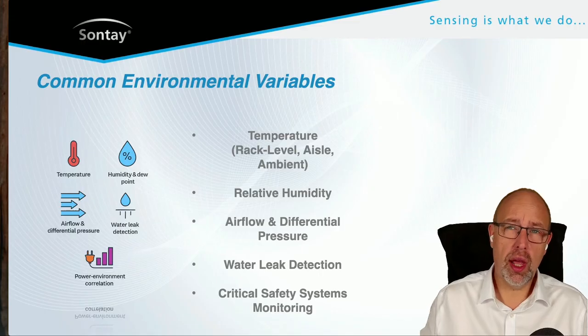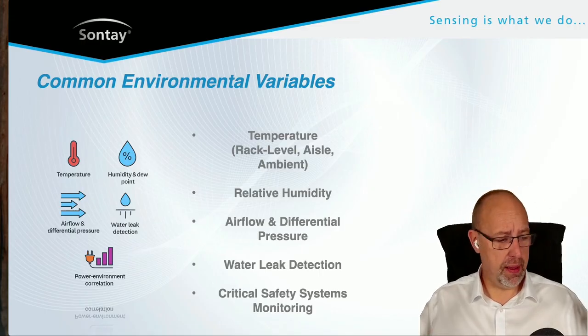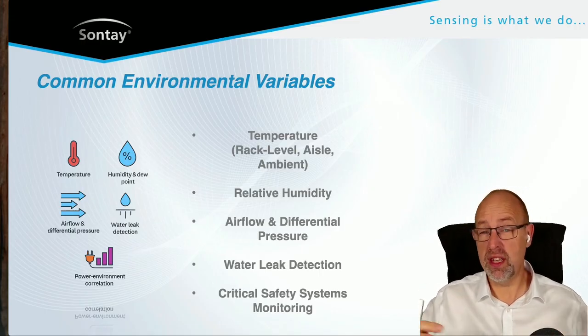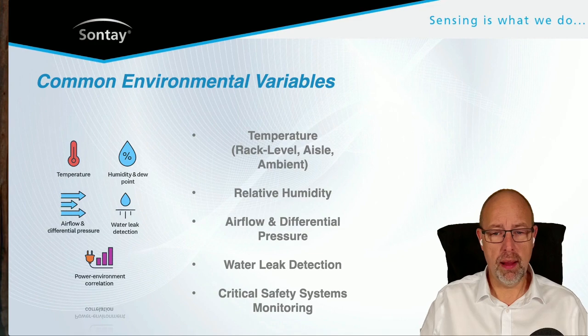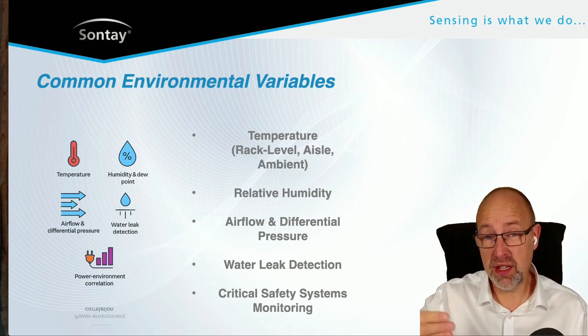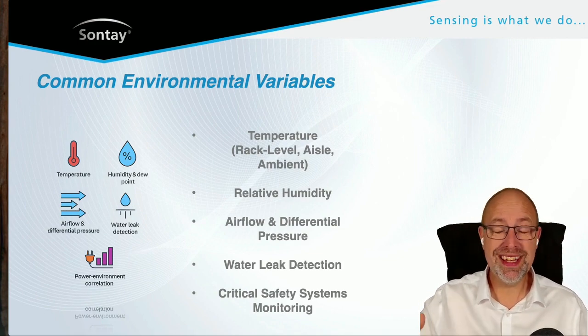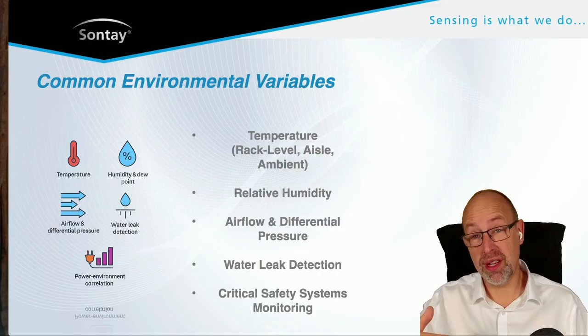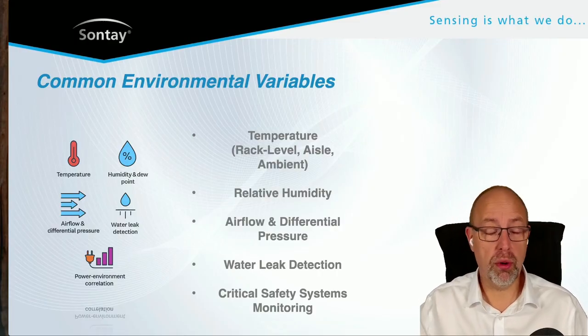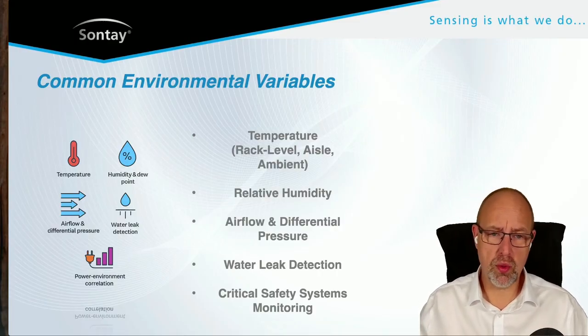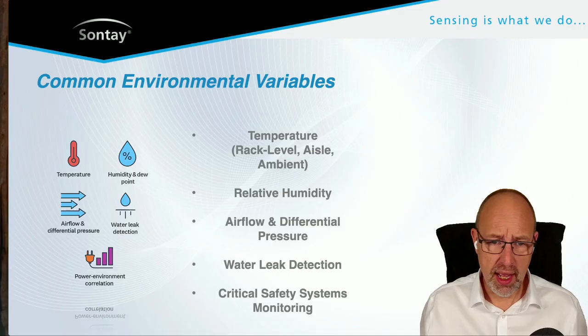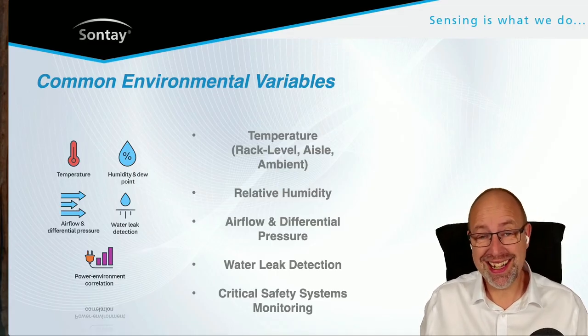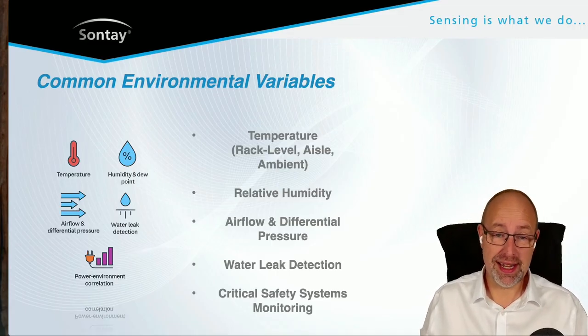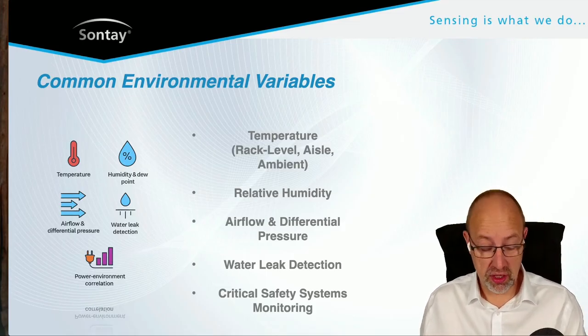Things like breakers also matter: a data center will have a PDU, a power distribution unit, containing many MCBs, miniature circuit breakers. You need to know if those have tripped or if there's a problem with the electrical supply. So there's a lot to monitor in a data center: temperature, humidity, leak detection, and the physical status of various components.